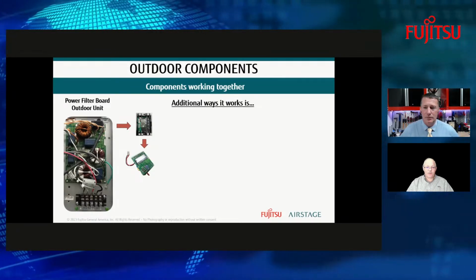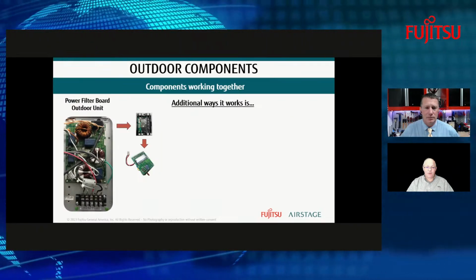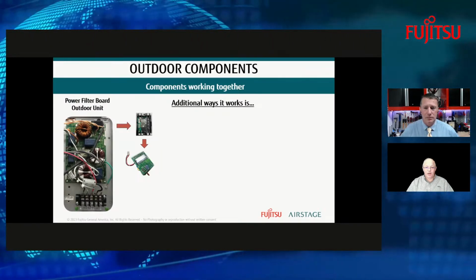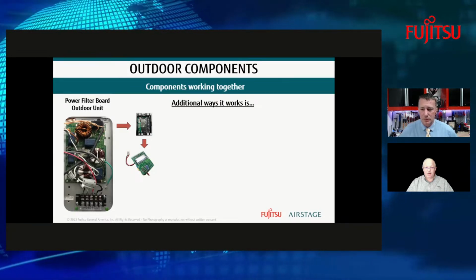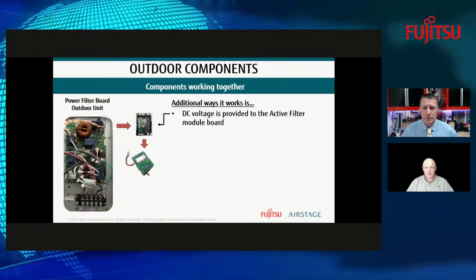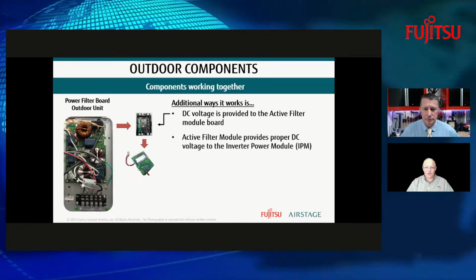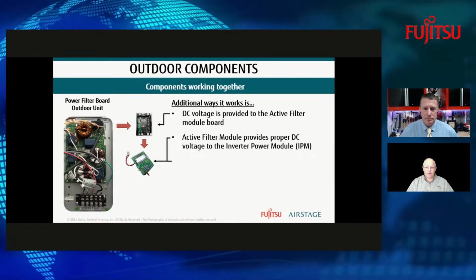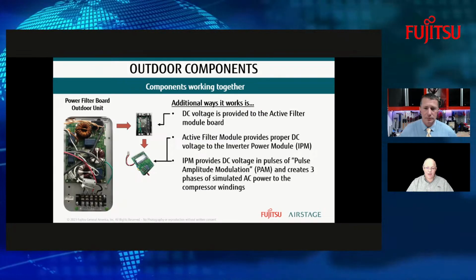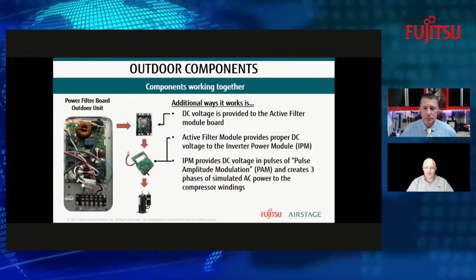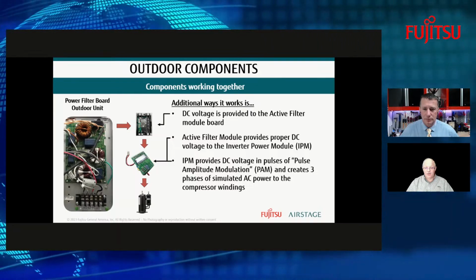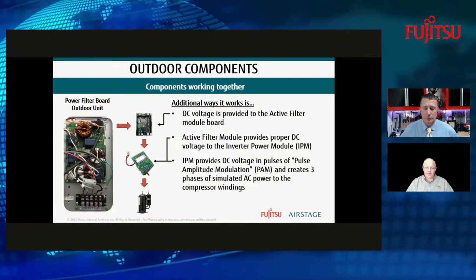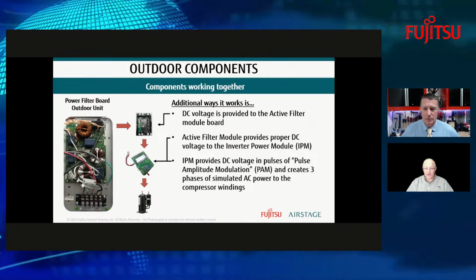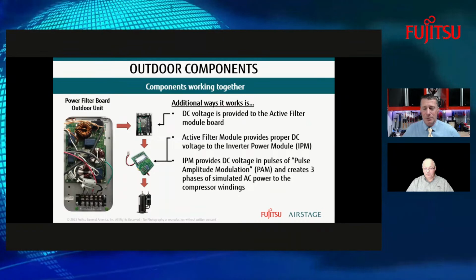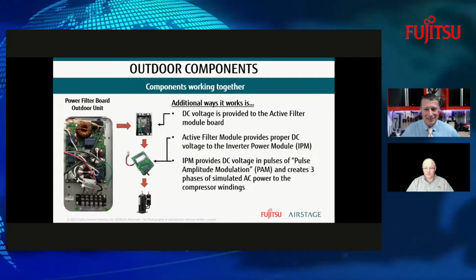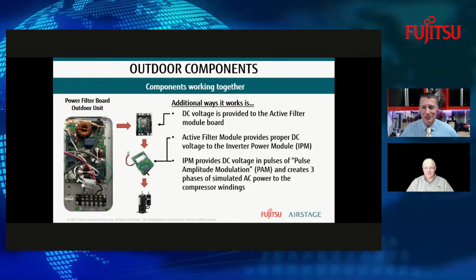So let's take you through this. We've got the power filter board. We went through the active filter module. We went into the IPM. So the DC voltage is provided to the active filter module. The active filter module is going to provide the proper DC voltage back to this IPM. And then the IPM is going to provide the DC voltage in pulses. And this is what creates that three-phase of simulated AC power to the compressor windings. Sure. And that's a question that gets brought up quite often. Is it AC or DC that is feeding our compressor motor?